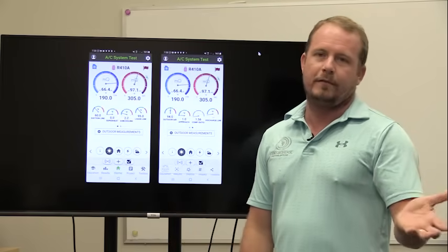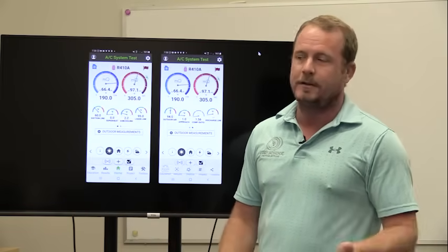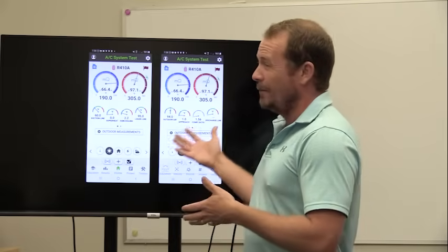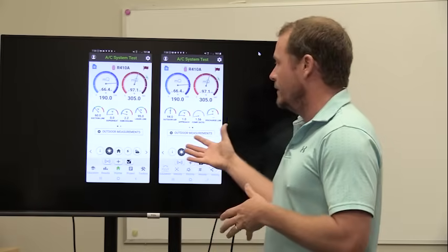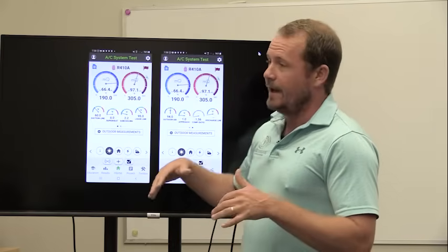So that means that what we're seeing in terms of compression ratio is actually going to be lower than what it really is, which is also why when you read in the books, a lot of times they'll tell you a compression ratio of three is going to be normal. That's because older equipment also had higher compression ratios, but it's also because we're not really measuring a true compression ratio, we're measuring something on the liquid line.